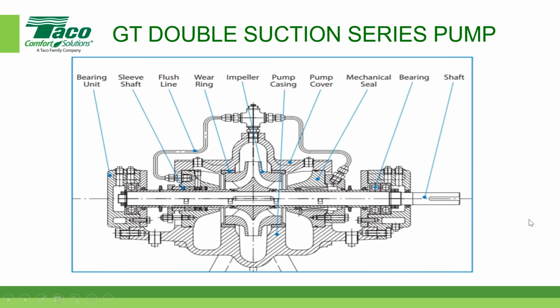Here's another one - I wanted to show a different type of cutaway. This one really explains the components so you can get some ideas. You can see the shaft that ties in - you'd think to the impeller, but it goes over to the motor through a coupler. This is the impeller right here. You can see these chambers feed into the impeller, which is why it's a double suction - you can kind of see that there.